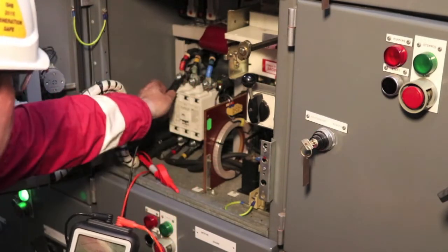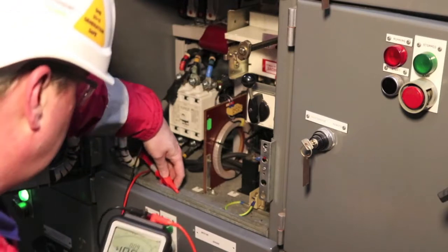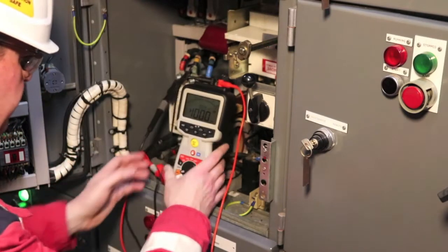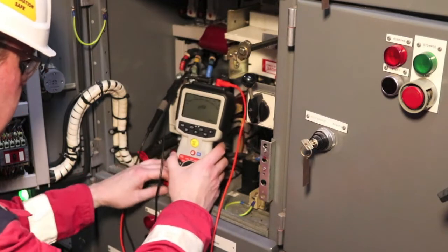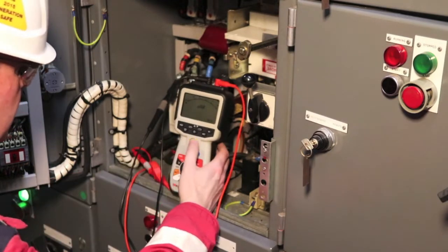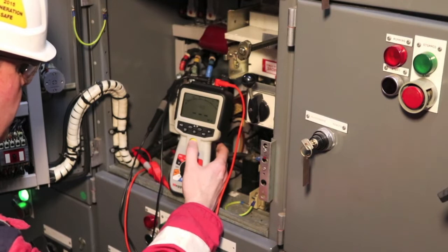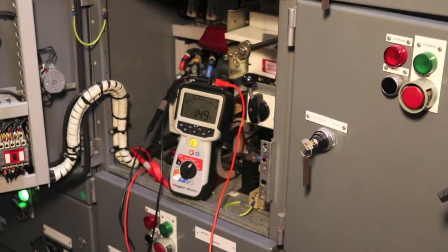So now set up for the first insulation test which will be dielectric absorption ratio test and turn it around to 500 volts. It's already saved from the last test on the dial setting so we'll just hit the test button and we'll leave it to record for the next one minute.